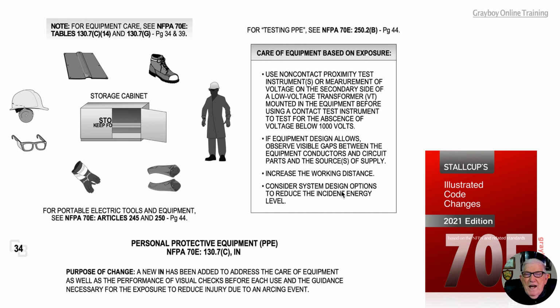Consider system design options to reduce incident energy level. What kind of system protective device should be installed ahead of the feeder or branch circuit? Are there current limiting fuses? Is it some kind of circuit reducing current limiting type device, such as a fuse listed in NEC 240.67? Is it a circuit breaker arrangement that reduces the energy level, such as outlined in 240.87?